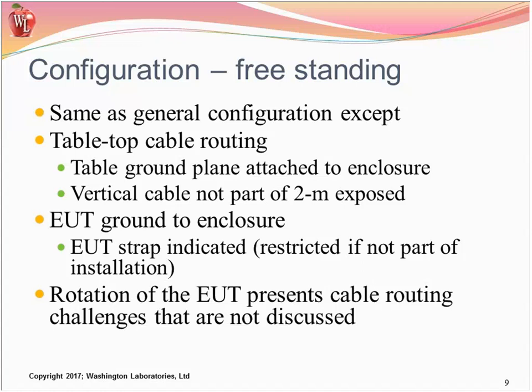The table ground plane is attached to the shielded enclosure, and so is the EUT, but we do have a loop configuration that does exist with this. The EUT is grounded to the enclosure, so the strap is there. It's restricted if it's not part of the installation. Now, this is the thing that gets away from us pretty easily. We attach artificial grounds because this generic configuration shows one. If that rack is not grounded any place, it should be placed on the isolation, 5 centimeters above the ground plane without a direct connection. If it's not part of the installation to put a ground strap in, you should not do it. The ground should be what you install. It should match the installation.